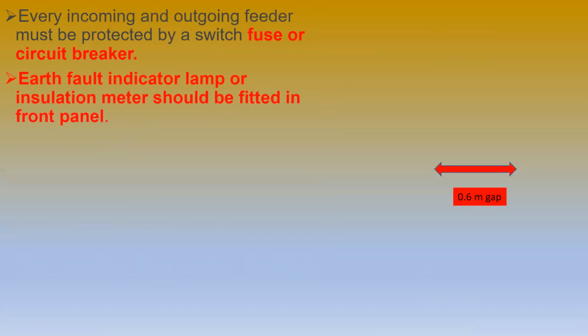So the earth fault indicator lamp or insulation meter should be fitted in the front panel. The insulation is measured by using a Megger, and that should be not less than 1 megaohm. So these meters, the ohm meter and this, are fitted in the front panel.